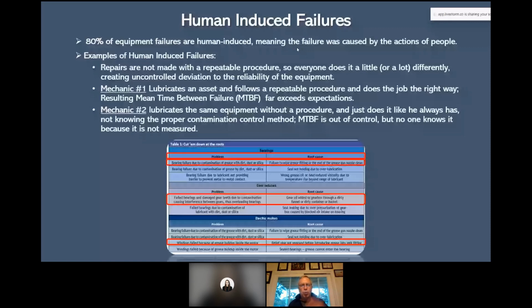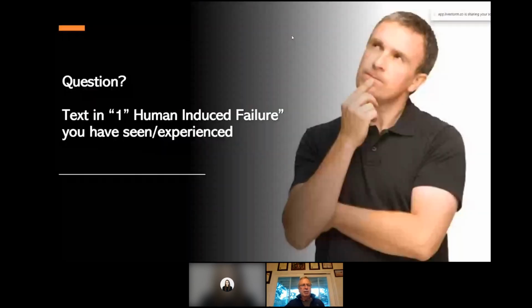What you're supposed to do is have the motor rotating as you pump grease into it. That's why you usually have an external line going out to it or some kind of pump for it, but you've got to have a relief plug. In other words, you've got to remove the plug underneath it or put a relief on it where it purges the old grease out. Gosh, amazing. So text in on this one: a human-induced failure you have seen or experienced. Just text it in.